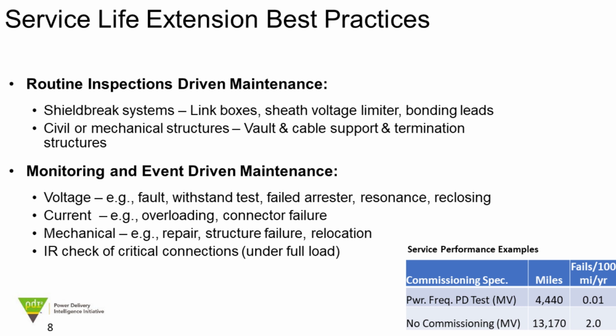So what are we looking at? Well, routine inspections could be looking at shield break systems for transmission systems. It could be looking at the civil or mechanical structures, the support structures. But really, we get to this monitoring aspect of this, and I know Landry has some thoughts on this on our next slide. But if you have an extreme voltage, say during a fault, or if you have a withstand test, or a failed arrestor, or some type of line resonance happening, or a significant amount of reclosing, cap bank switching, and so forth, these kinds of events, if not well protected, if arrestors are not doing their job, our systems are seeing extreme voltage. And as a cable ages, the AC breakdown, the ability to withstand extreme voltage, drops substantially. And if we're not protecting our system, not just how it's going to be as installed, but as it's performing during service and as it ages, we will start to see new issues show up.